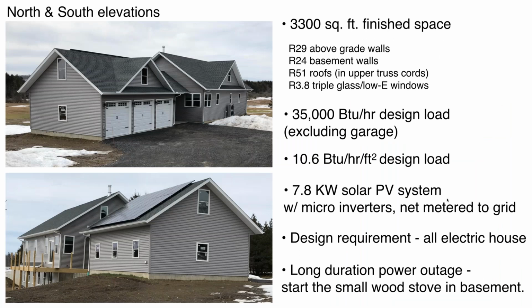There's the photographs. You can see it's got a 7.8 kW PV system on it. It is net metered, so a lot of the electricity that is used to run the heat pump is already being produced by that PV system. It does have very good insulation. If you look at the R values here, 3,300 square feet of space at a design load of roughly 35,000 BTUs per hour is just over 10 BTUs per hour per square foot of floor area at design load.